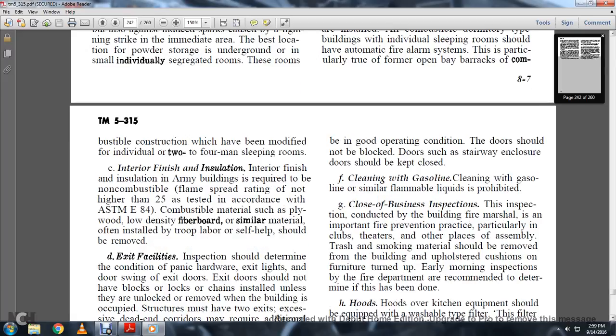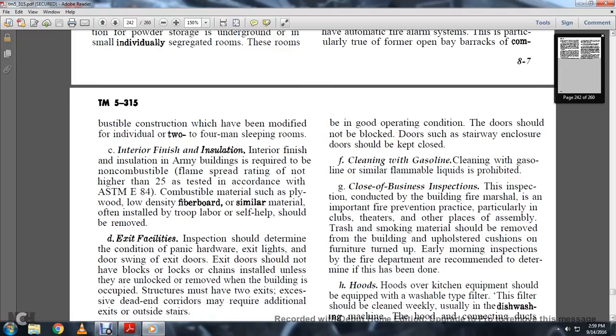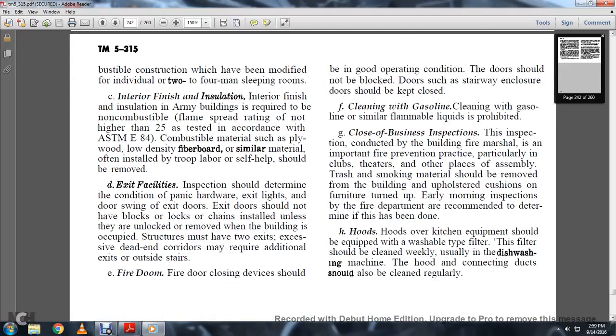Interior finishing and insulation. Interior finishing and insulation in army buildings are required to be non-combustible, with a flame spread not higher than 25 as tested in accordance with ASTM E84. Combustible materials such as plywood, low density fiberboard, and similar materials, often installed with troop labor or self-help, should be removed.